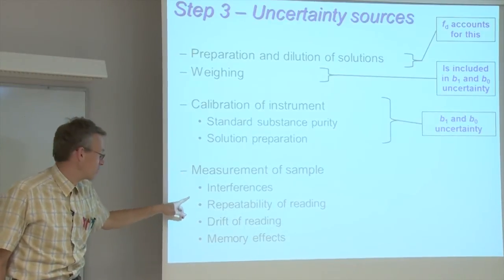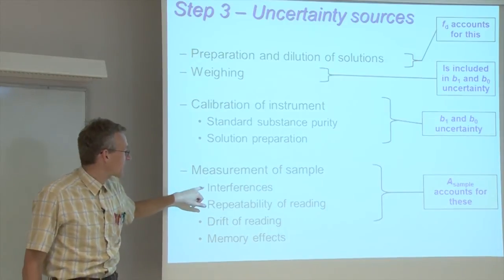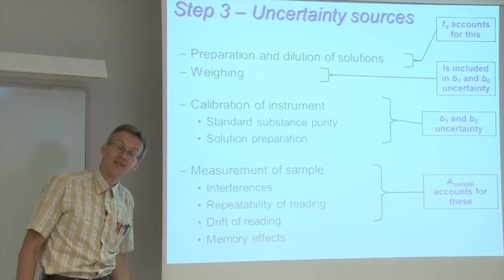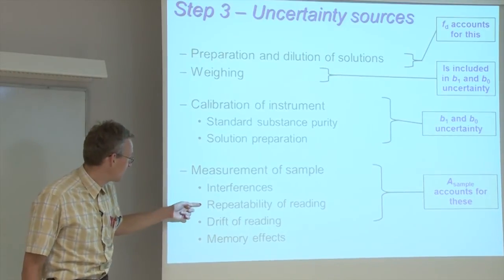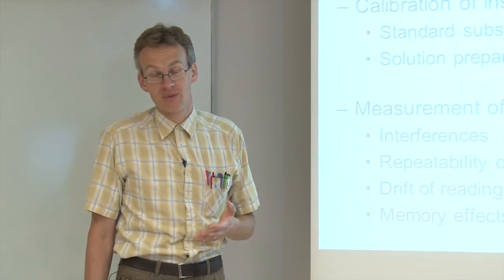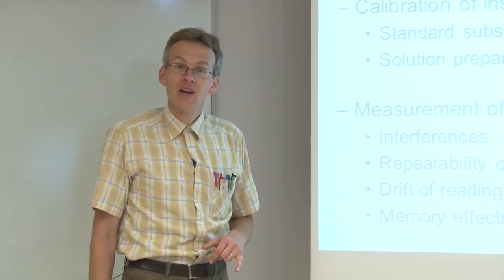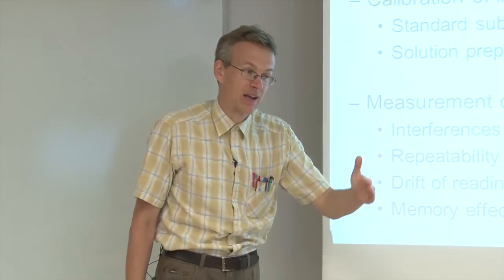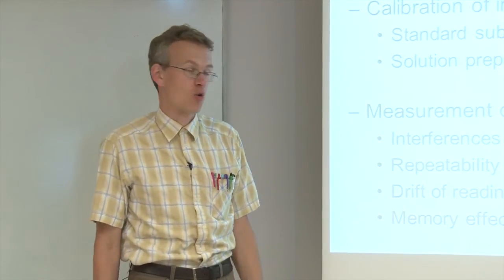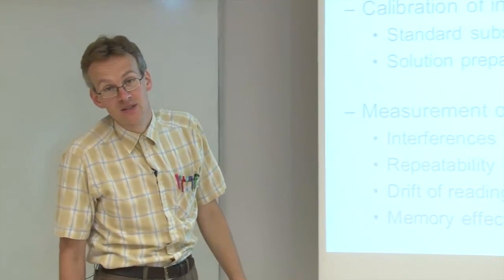Finally, the measurement of the sample itself — meaning the photometric measurement with the sample solution. There can be interferences from other components in the sample that also absorb radiation, thereby giving increased results. The repeatability of the reading is of course a factor, meaning that if we measure the same solution absorbance several times, we get slightly different results. And finally, drift of the reading: if we measure with some time lag, we can get systematically different results because the properties of the spectrophotometer slightly change over time. All these effects are taken into account by the input quantity A_sample, the sample absorbance.